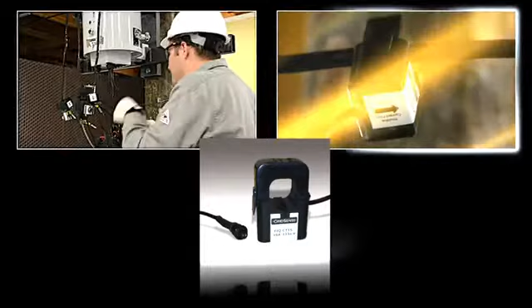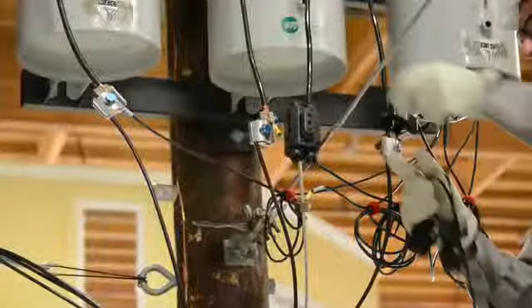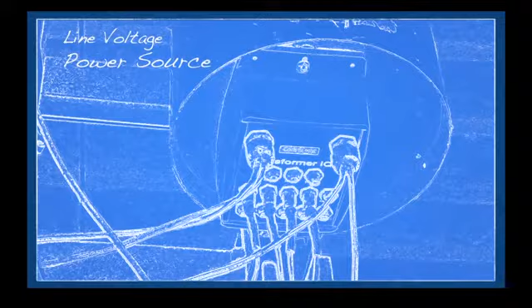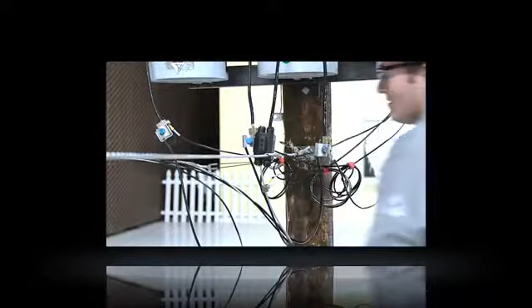Rogowski coils, or clip-on CTs, measure current flow from the transformer. For this application, we will use the more cost-effective CTs. You attach one for each phase and the neutral. The arrow should point in the direction of the load. Transformer IQ is powered via line voltage, so it doesn't require an external power supply. For this application, the A, B, C, and neutral voltages will need to be directly connected to the Transformer IQ using the 10-gauge wires supplied.